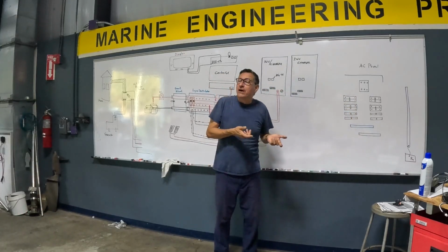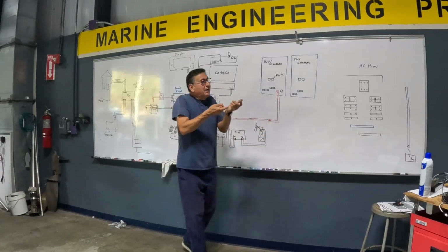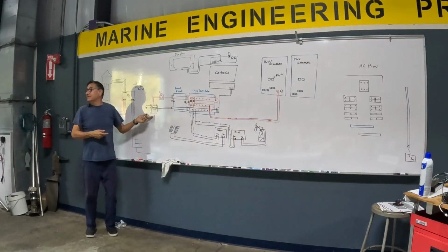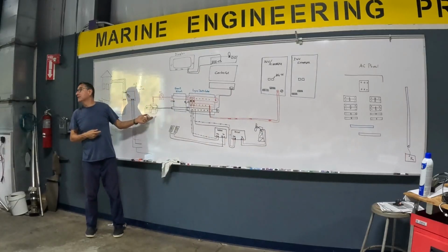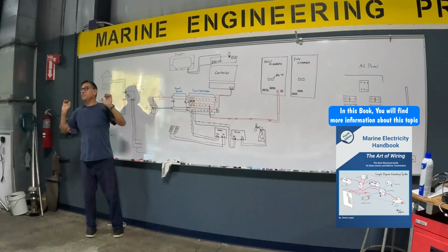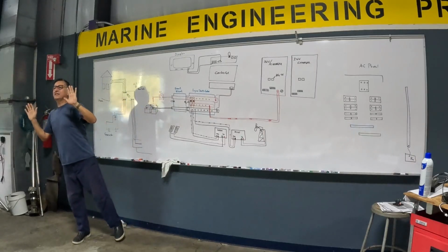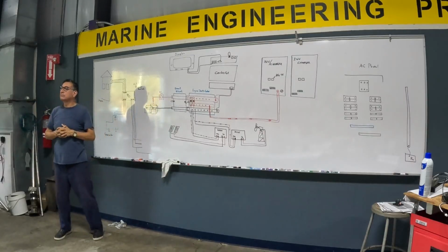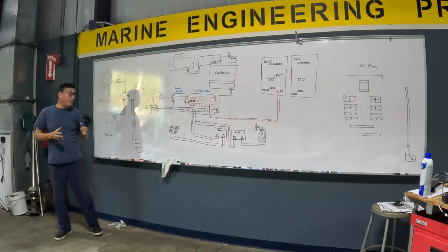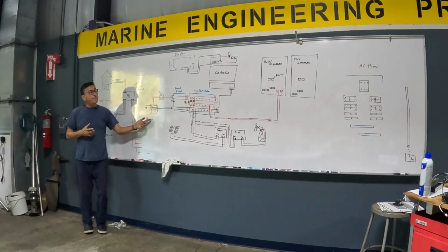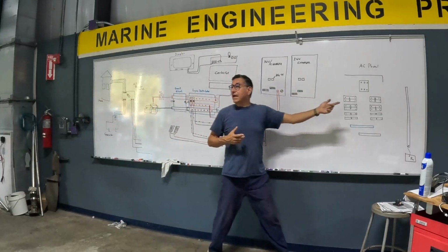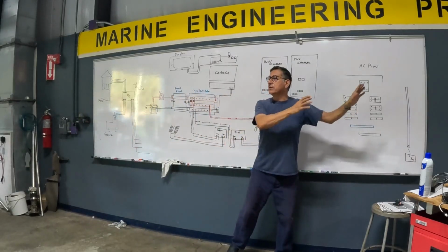Oh, I need to provide in the input in the battery bank 7,000 plus 20% of DC power in order to be 100% sure that in the output of the AC I have 7,000. This is an example. That's okay, guys? The capacity of this battery bank depends on the AC output that I require in the panel.